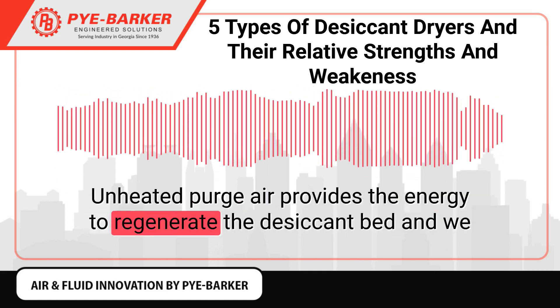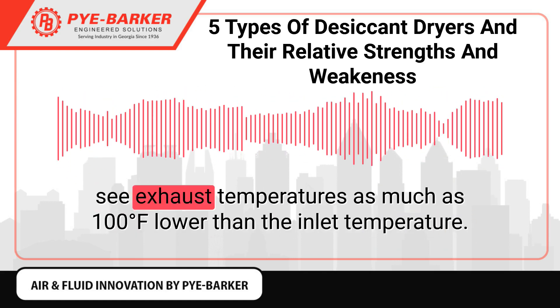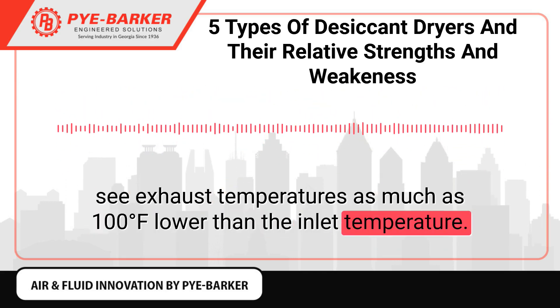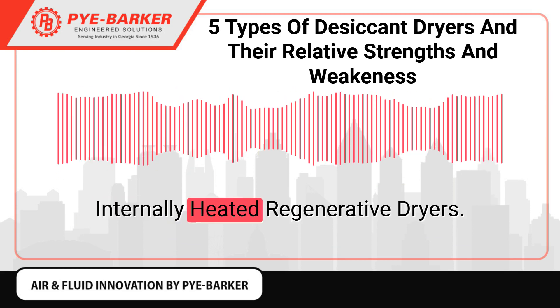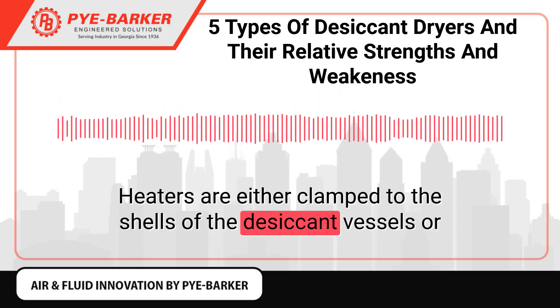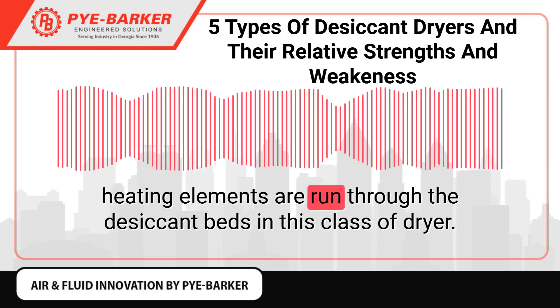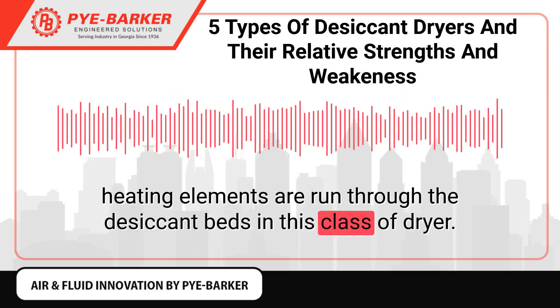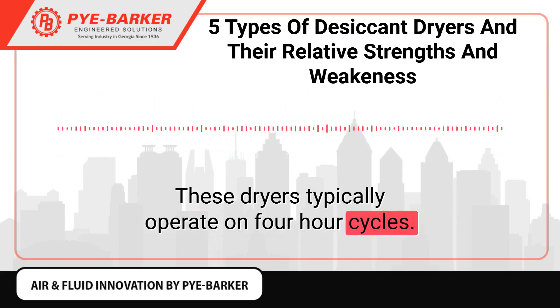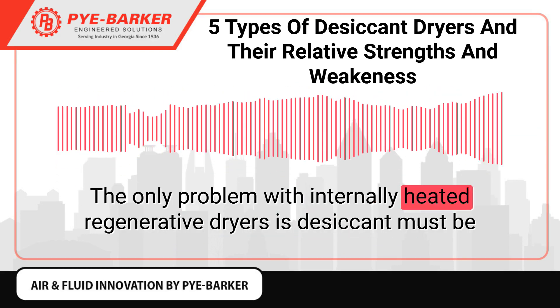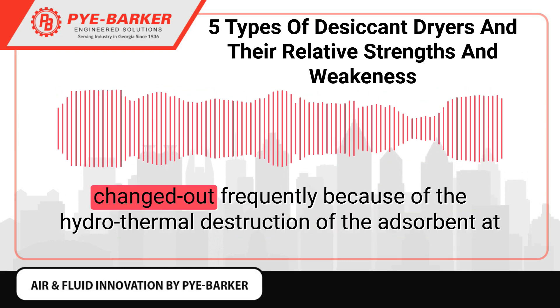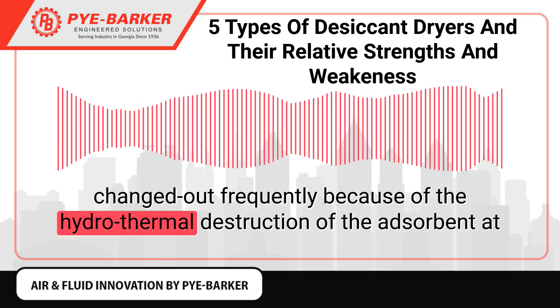Unheated purge air provides the energy to regenerate the desiccant bed, and exhaust temperatures can be as much as 100°F lower than the inlet temperature. In internally heated regenerative dryers, heaters are either clamped to the shells of the desiccant vessels or heating elements are run through the desiccant beds. These dryers typically operate on four-hour cycles. The main drawback is that desiccant must be changed out frequently due to hydrothermal destruction of the adsorbent at elevated temperatures in moist environments.